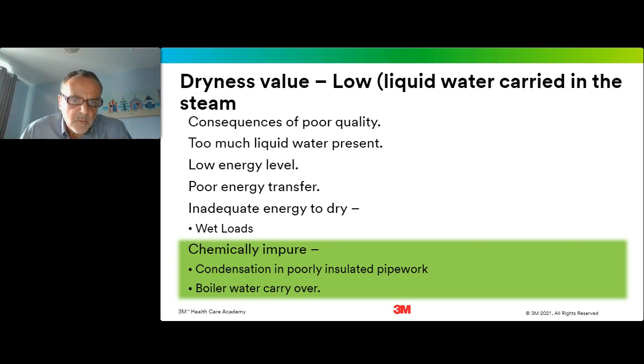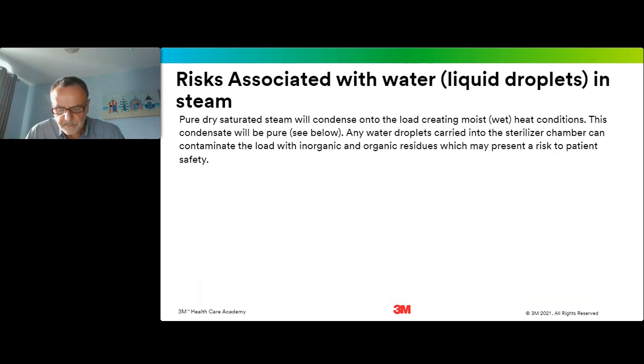Of course, of more concern to us today is the chemical impurities present in these small droplets of liquid water that are present in steam with a low dryness value. And the first problem might be water arising from condensation of the steam in poorly insulated pipework, or indeed it might be boiler water which is carried over with steam as the steam is generated. So let's have a look at that in a bit more detail.